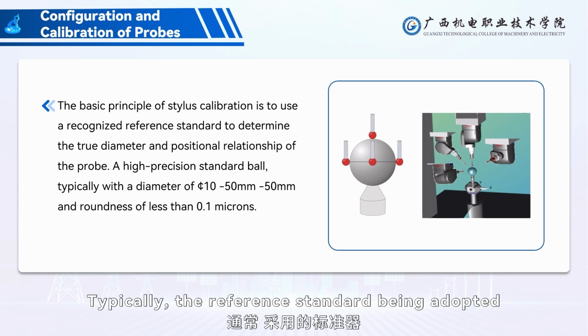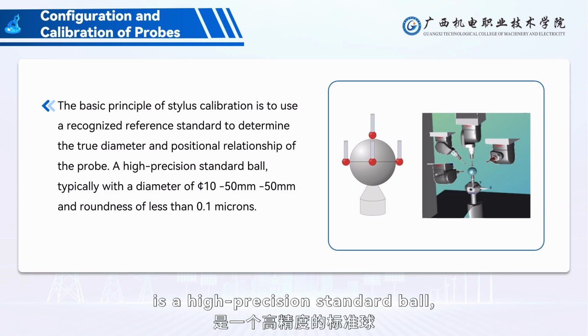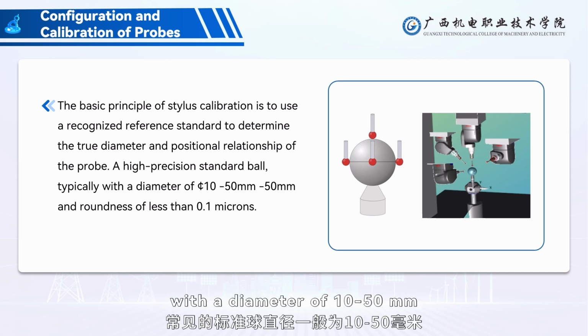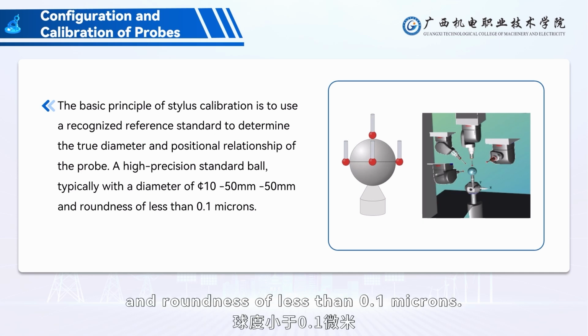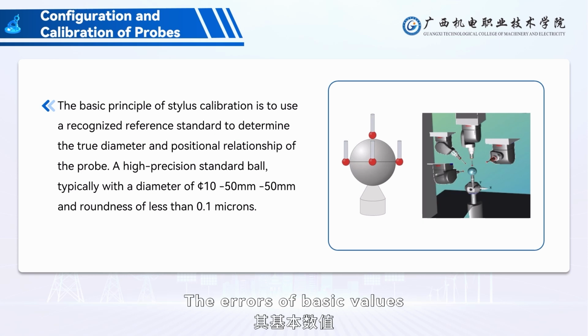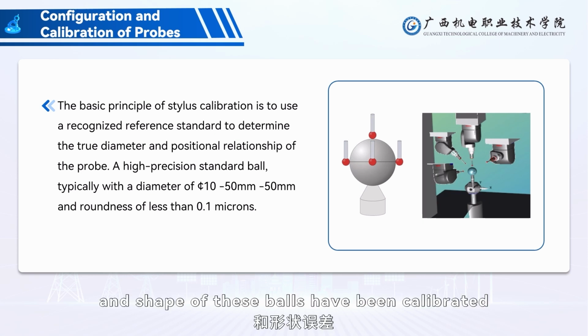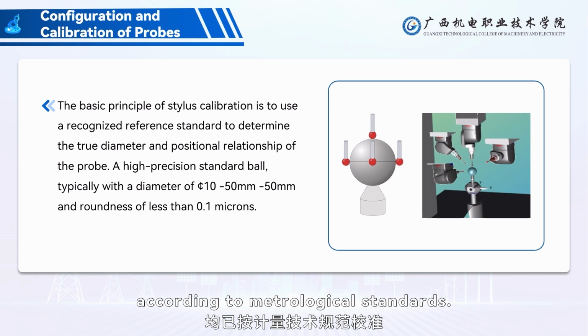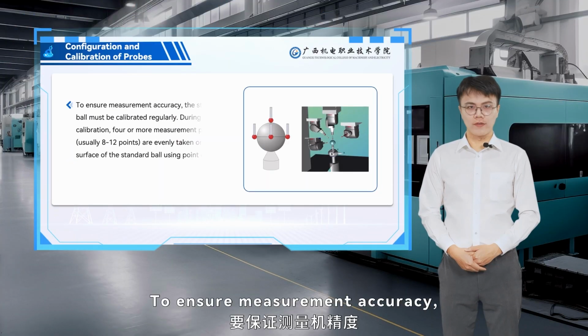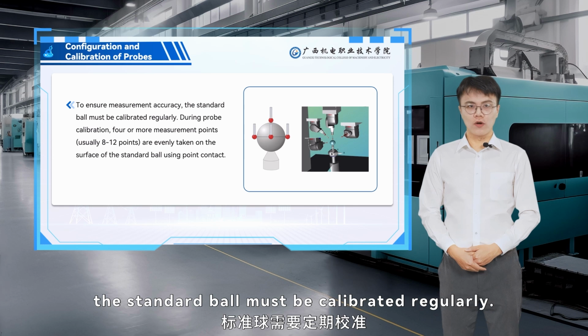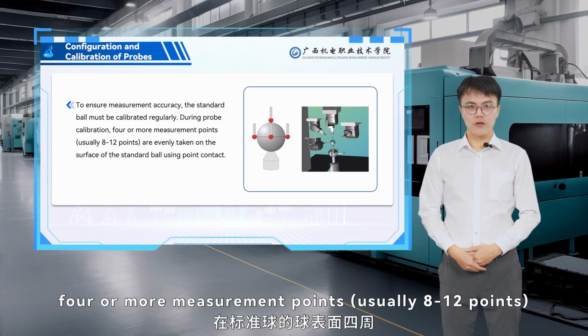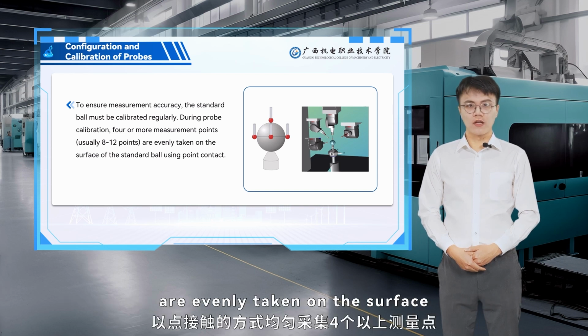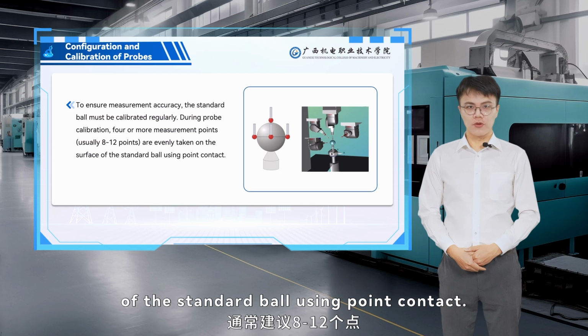Typically, the reference standard being adopted is a high-precision standard ball, with a diameter of 10 to 50 millimeters and roundness of less than 0.1 microns. The errors of basic values and shape of these balls have been calibrated according to metrological standards. To ensure measurement accuracy, the standard ball must be calibrated regularly. During probe calibration, 4 or more measurement points, usually 8 to 12 points, are evenly taken on the surface of the standard ball using point contact.